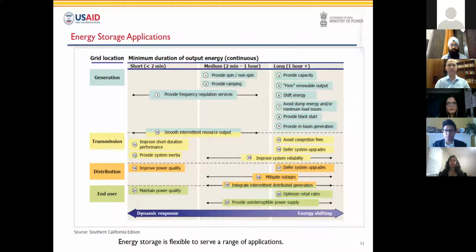Storage is used to provide capacity and also be co-located with renewables, especially solar, because of the host of benefits it brings - shifting energy, capturing energy that would otherwise be wasted, or smoothing the output of an otherwise intermittent system. At the transmission and distribution level, storage can solve specific network issues, like providing voltage support, reactive power support, and so on, and also help distribution operators defer expensive upgrades, which is an indirect cost saving passed on to the developer.